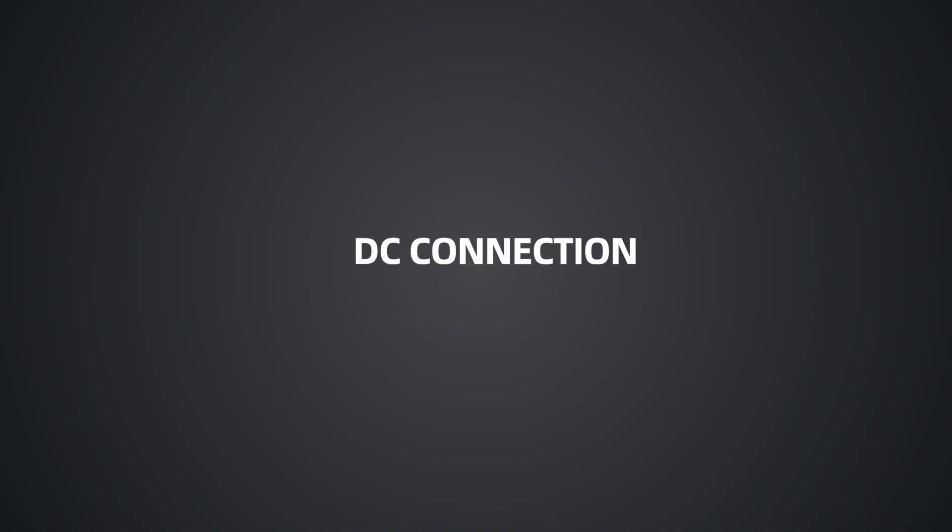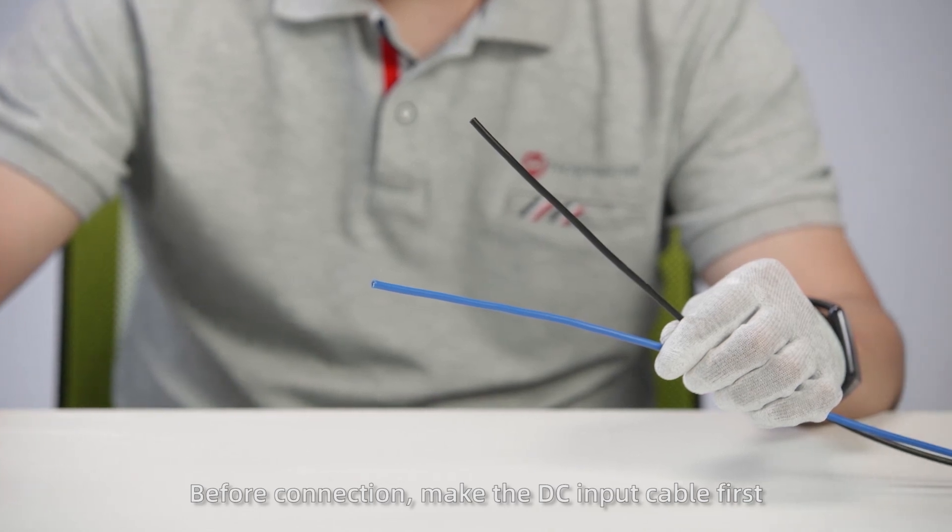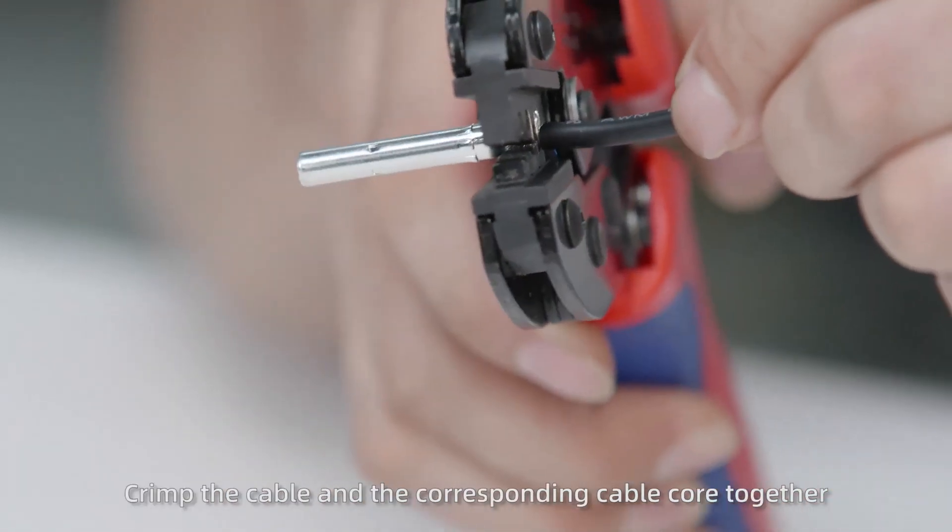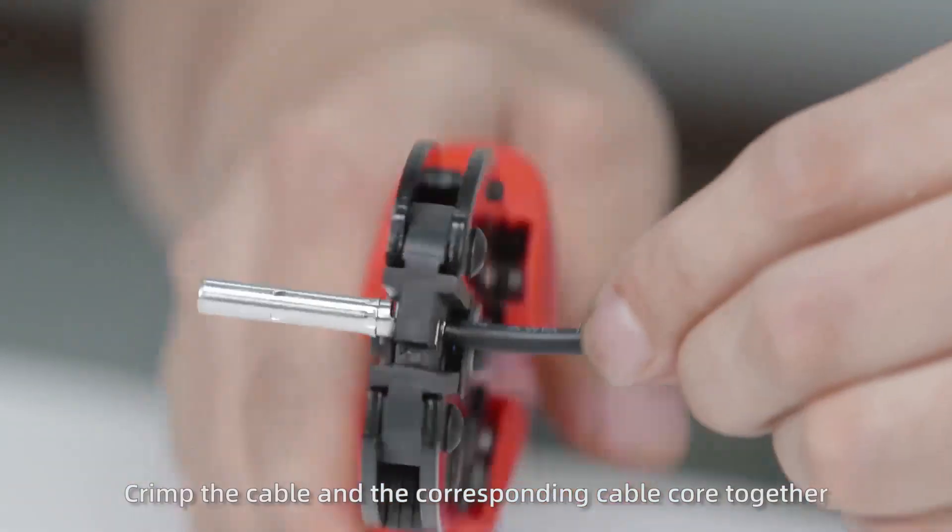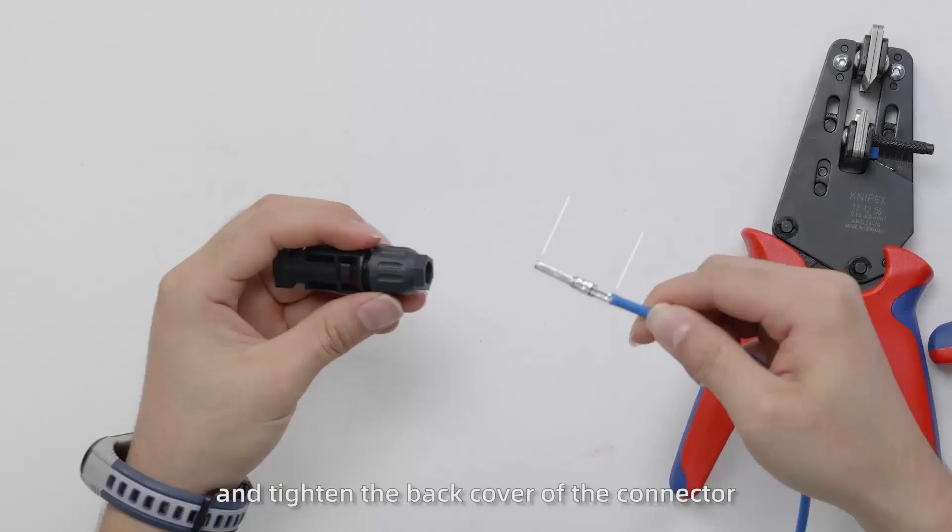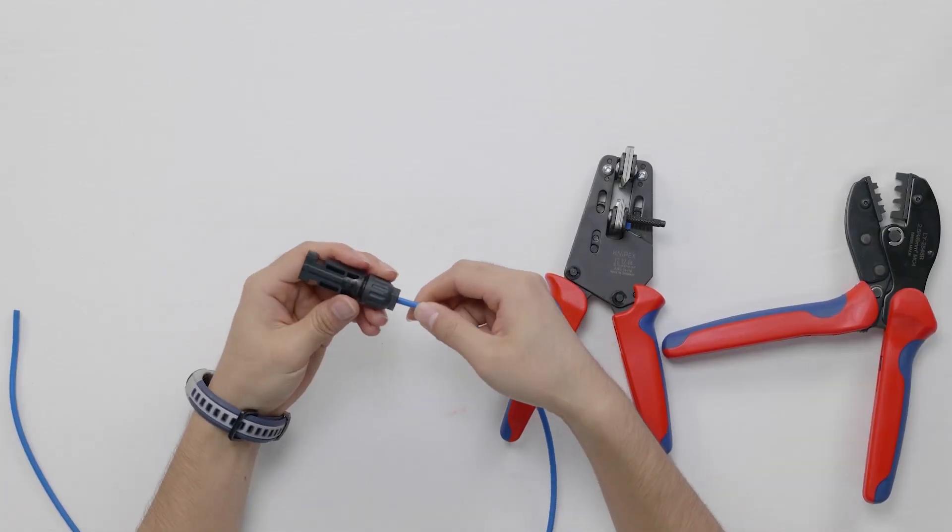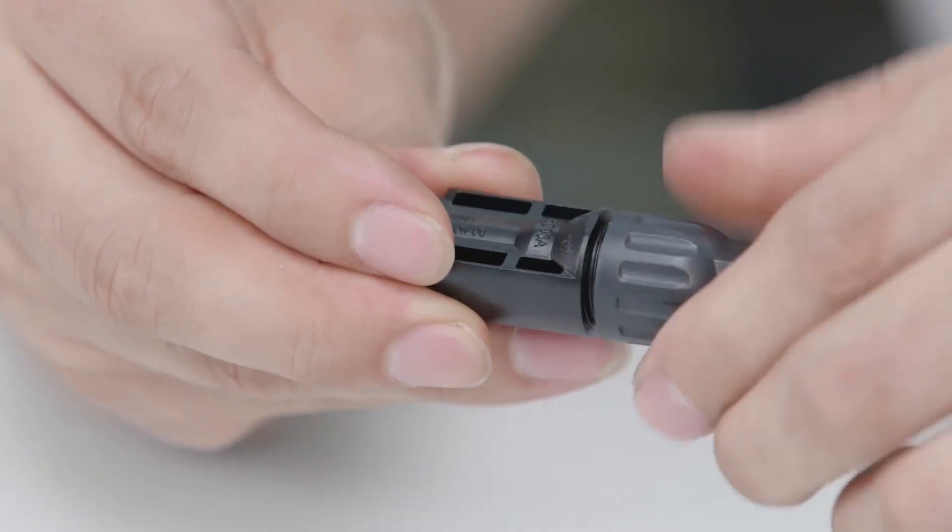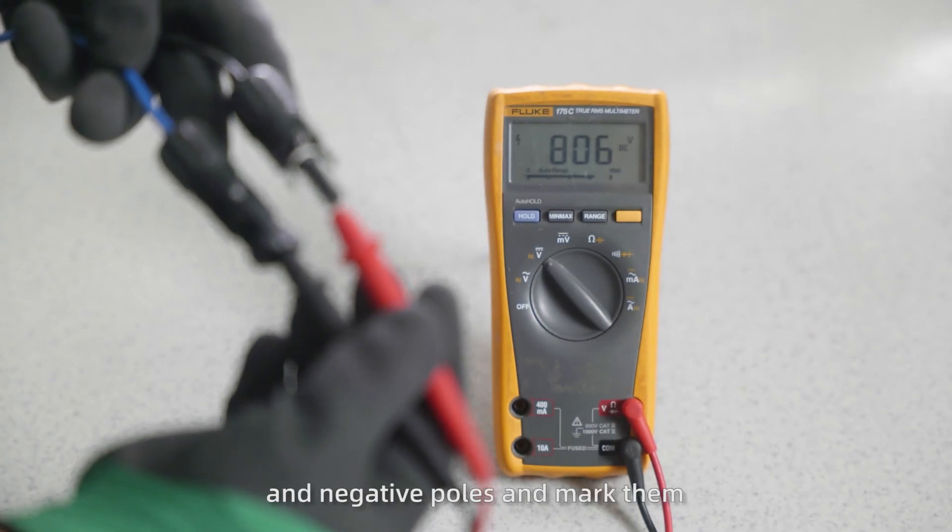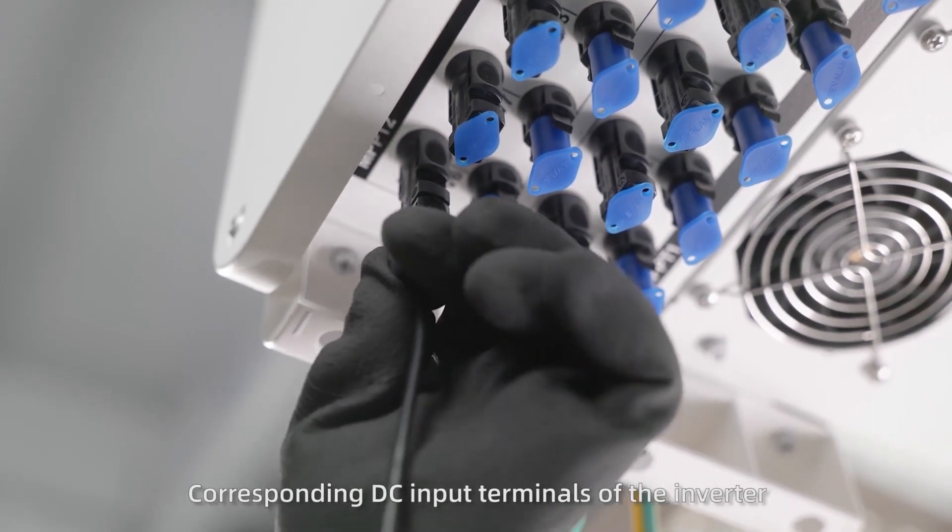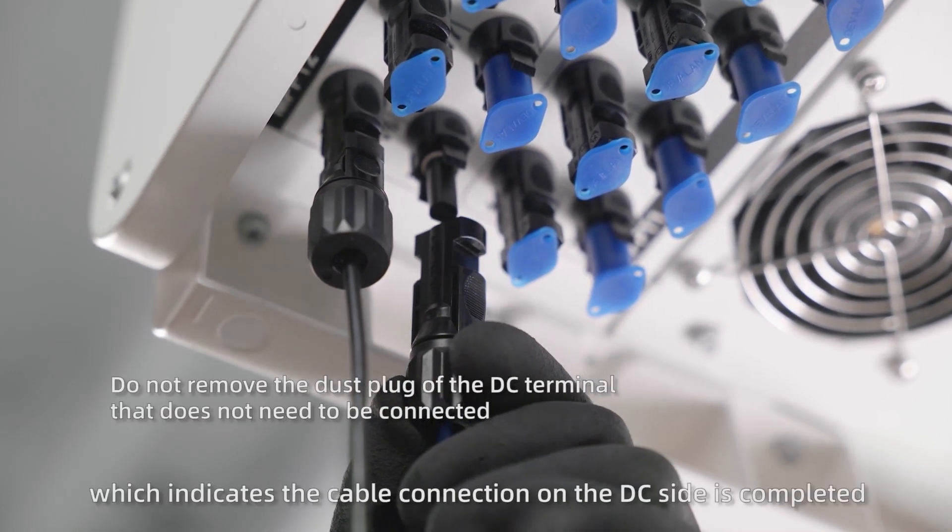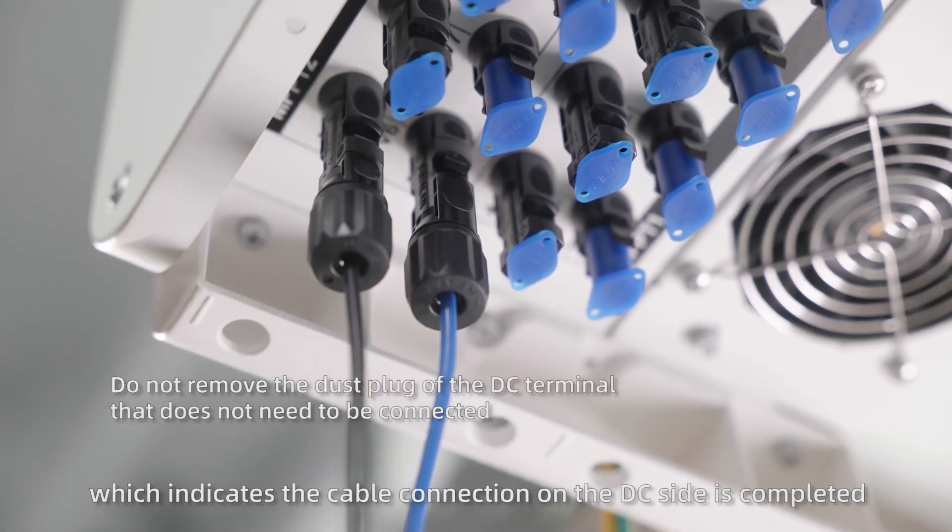Finally, connect cables on the DC side. Before connection, make the DC input cable first. Confirm the positive and negative poles of the input cable. Then use a wire stripper to strip the cable. Crimp the cable and the corresponding cable core together. And finally insert the cable core into the male and female poles of the MC4 connector according to the correct polarity. After the DC input cable is completed, use a multimeter to determine the positive and negative poles and mark them. Then insert the positive and negative connectors into the corresponding DC input terminals of the inverter. When you hear a sound of click, the terminal is connected in place, which indicates the cable connection on the DC side is completed.